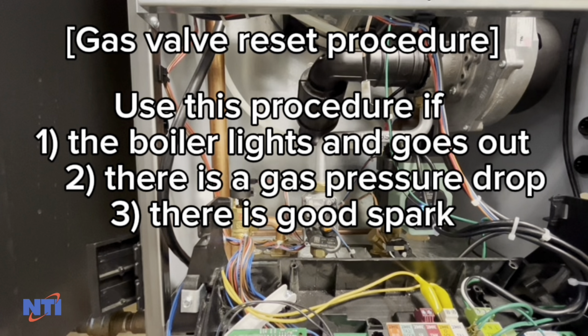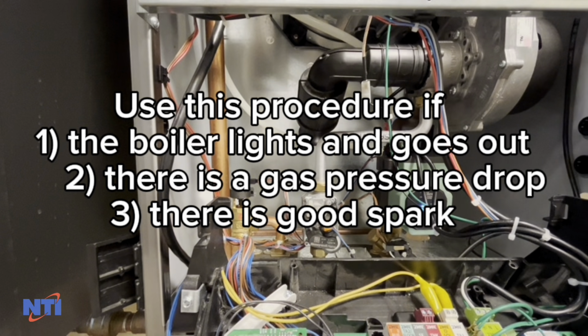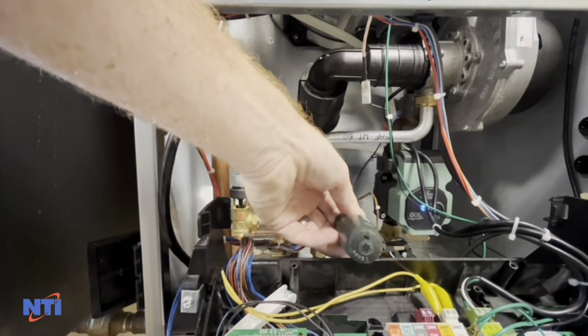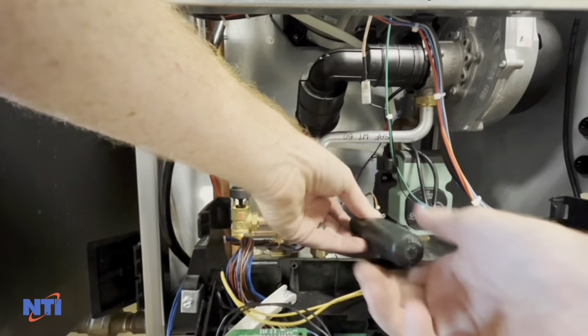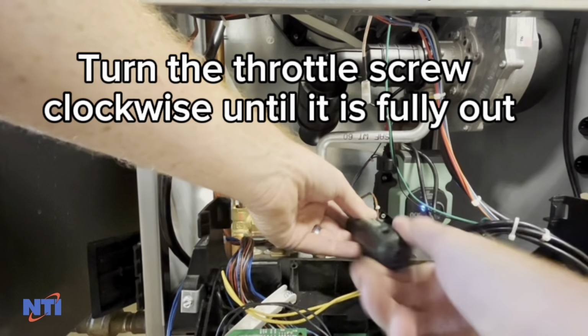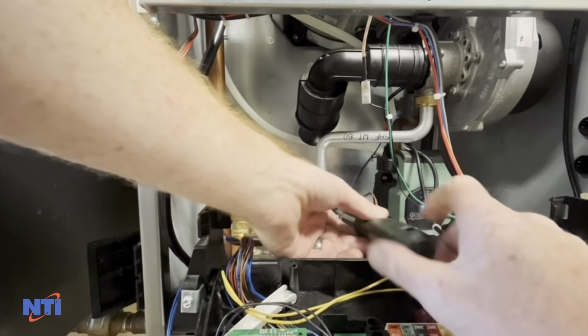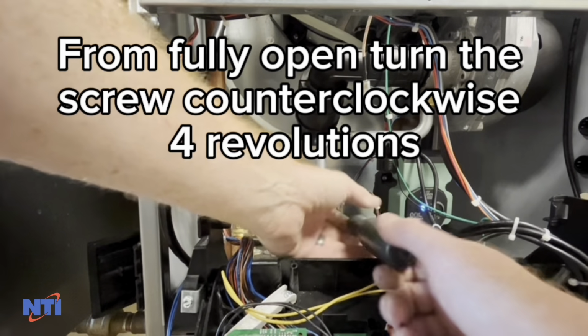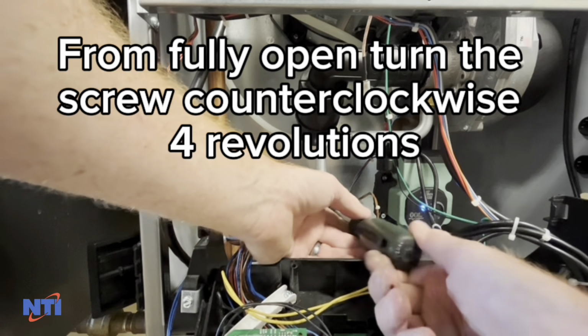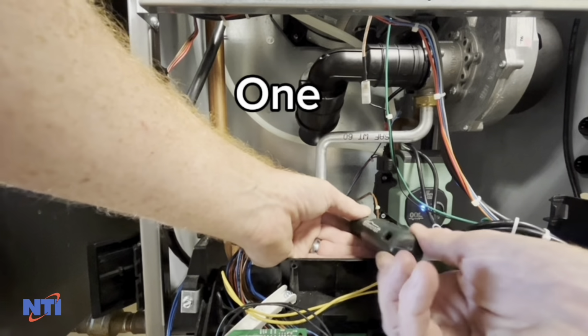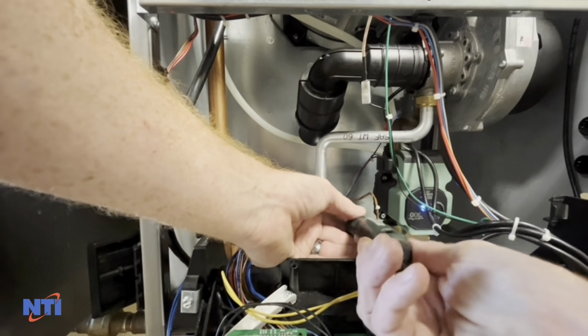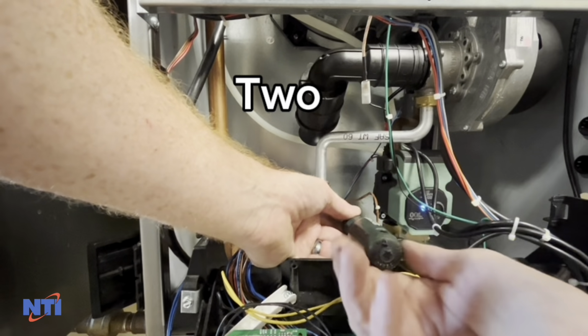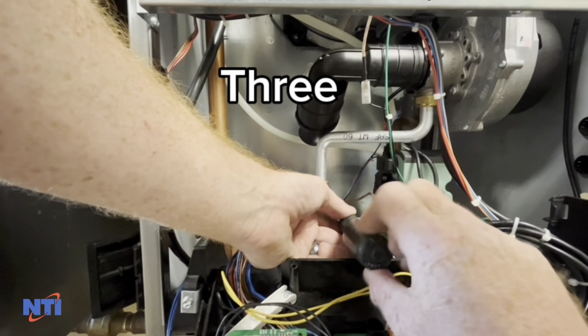We have established proper spark, inspected the venting for blockages. We are sure there is a good gas pressure drop indicating a proper supply of gas to the boiler. At this point, a gas valve reset can be performed. Turn the throttle screw clockwise until it is fully open. From the fully open position, go 4 turns counterclockwise to set the valve to an approximate factory starting point.